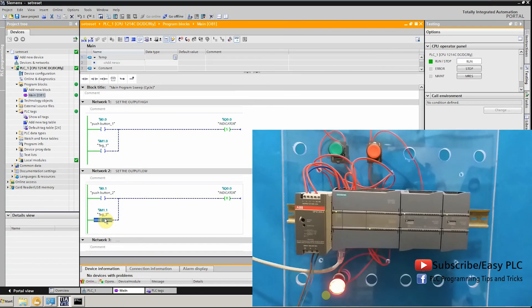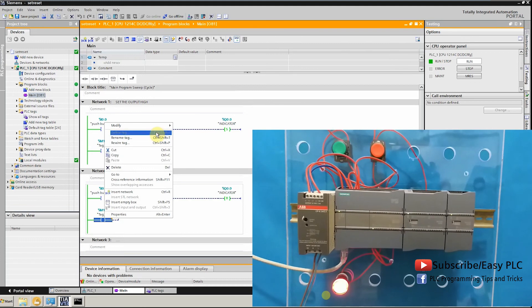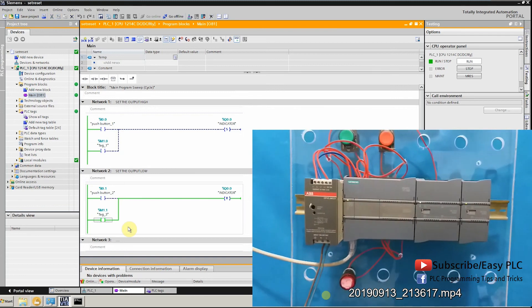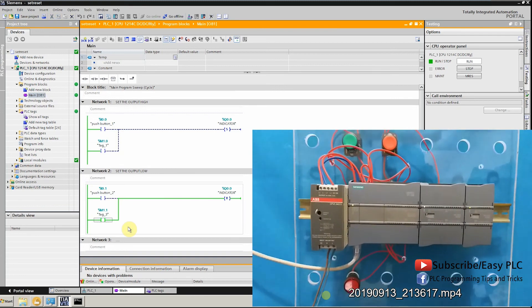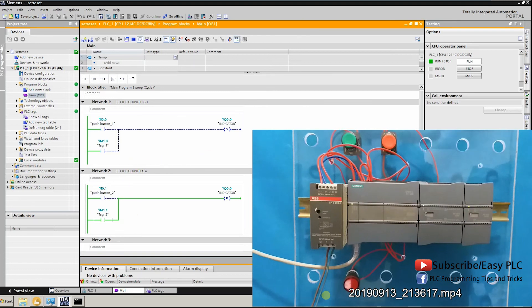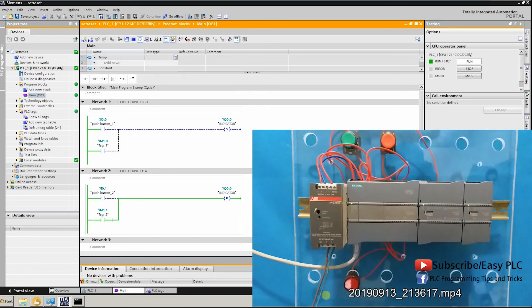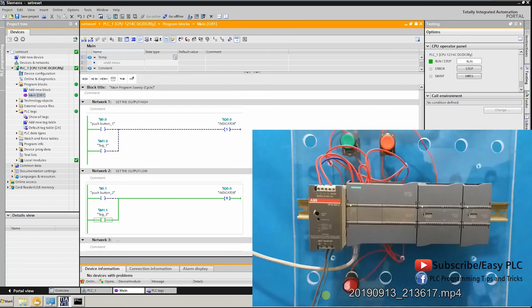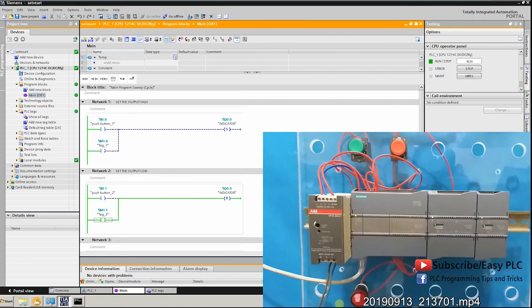There is a condition we need to observe carefully. Memory bit M1.1 is high and the reset instruction is forcing the output LED indicator to low state. If we now change the state of memory bit M1.0 to high using CTRL and F2, it will reset the indicator LED state to low. Remember, reset instruction has priority over the set instruction — meaning if the reset instruction is high, the set instruction cannot change the state of the output to high.